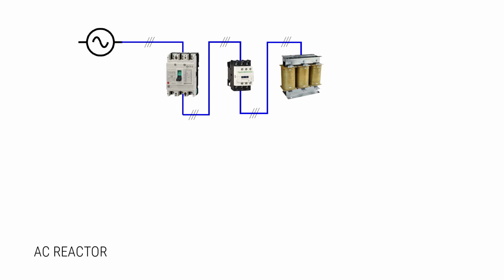AC reactor. When power capacity is significantly large compared to inverter capacity, or when the power factor needs to be improved, externally connect an AC reactor. Many VFD manufacturers install reactors in the drives. It is always a good idea to check.